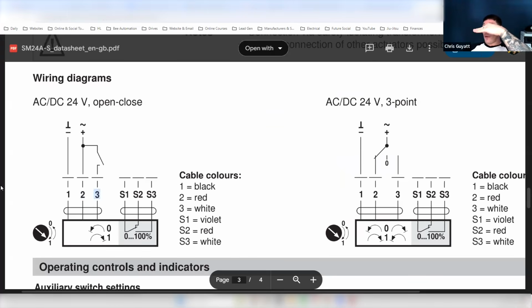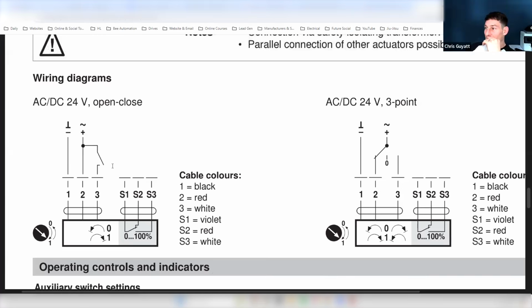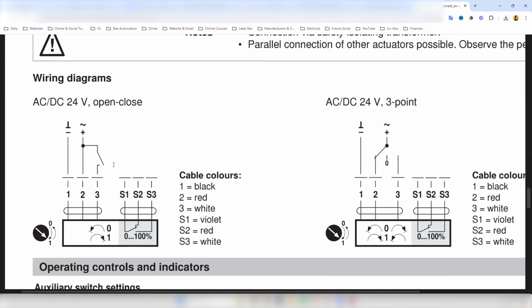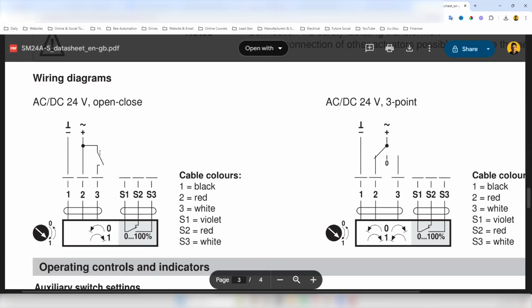As soon as we remove that power on 3 and we open this circuit again, whether that's a relay on a PLC or a switch on the front of the panel, as soon as we remove that, the damper's going to close again. Make sense? So that relay then will get a signal perhaps from our PLC, for example. So you may have an input device that goes back to the PLC and says, okay, we need some fresh air. That will then send the signal out to this particular relay to force it closed. Yeah, that kind of process.